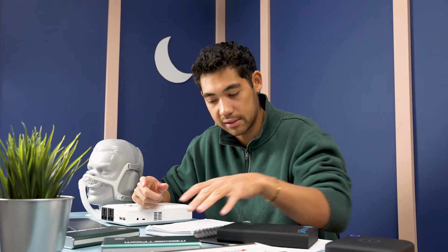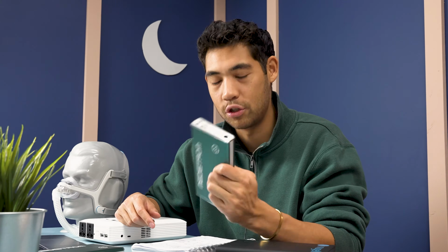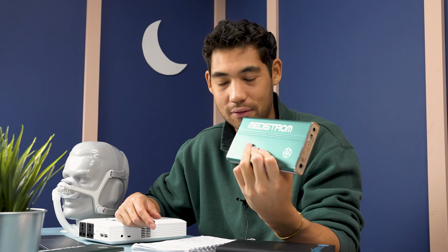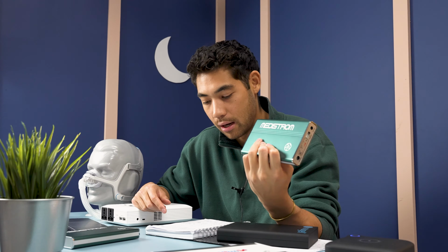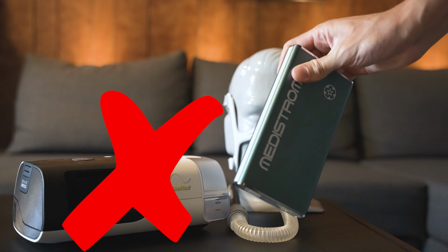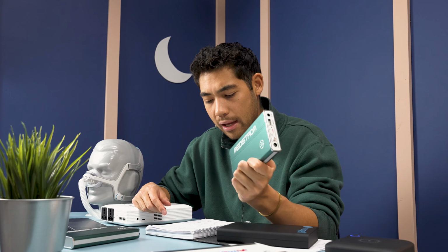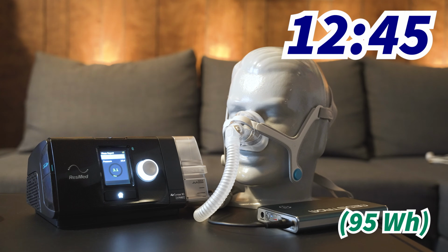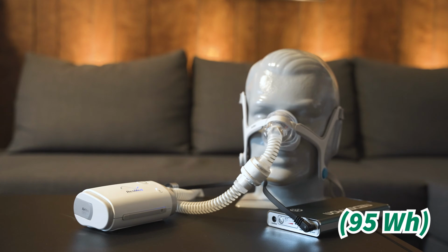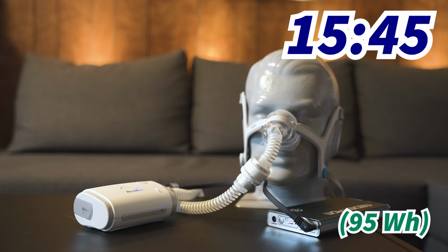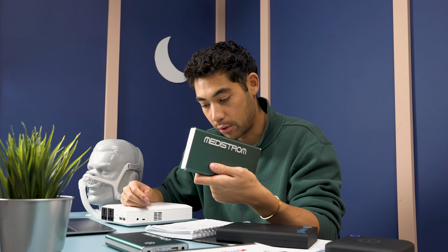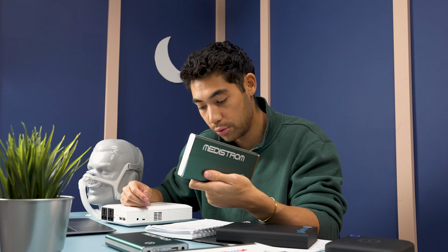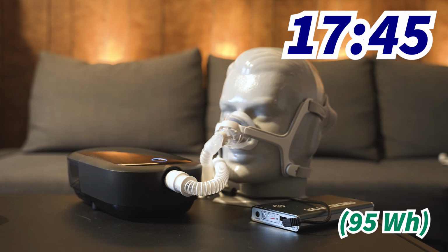The MediStrom 24 volt I tested on the AirSense 10 and the Air Mini. You had to buy a separate cable to run an AirSense 11, which is really dumb, so I didn't actually test it on that. It ran the AirSense 10 for 12 hours 45 minutes and the Air Mini for 15 hours 45 minutes. Next, the MediStrom 12 volt, which I only ran on the DreamStation 2 since it can't run anything else, lasted 17 hours 45 minutes, really good there.